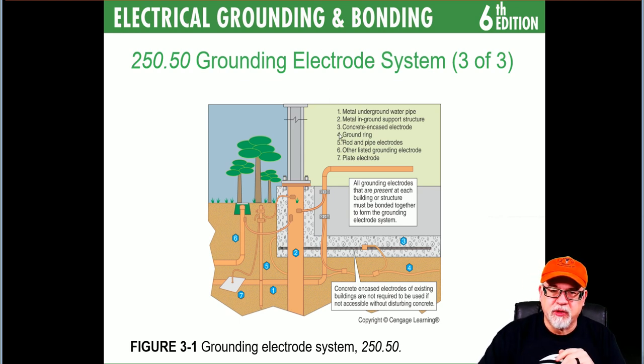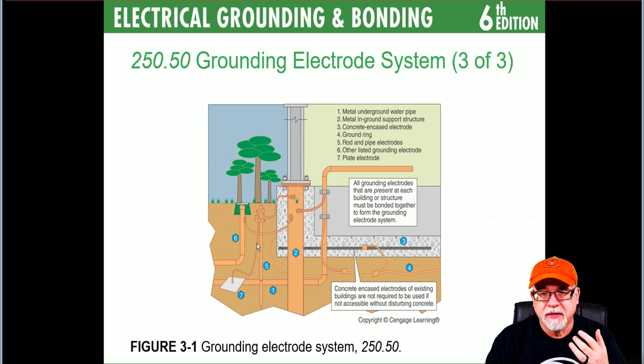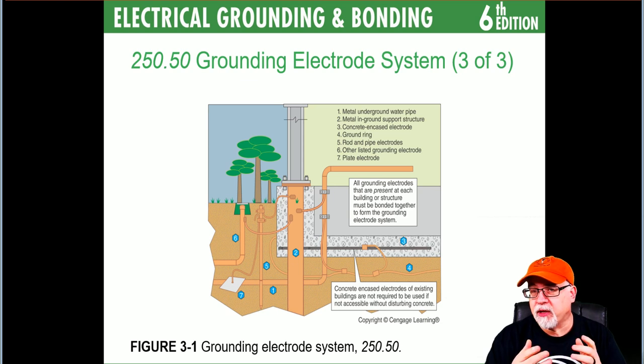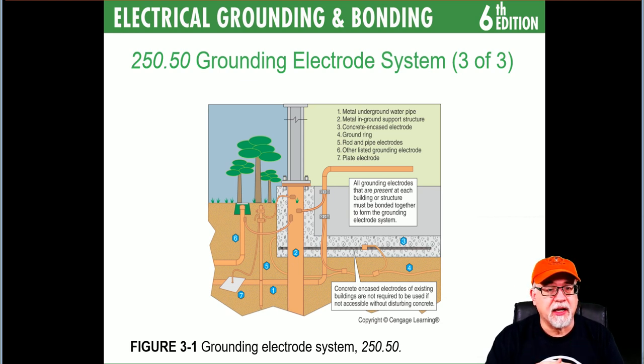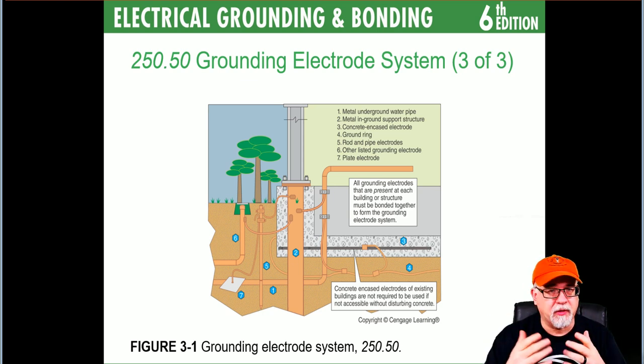Number five is probably the most common — the ground rod or pipe type electrode, driven eight feet in contact with the earth. If you hit rock, you can do it at a 45-degree angle. If you hit rock again, you can dig a trench and put it in that way. We cover that in the program in depth.